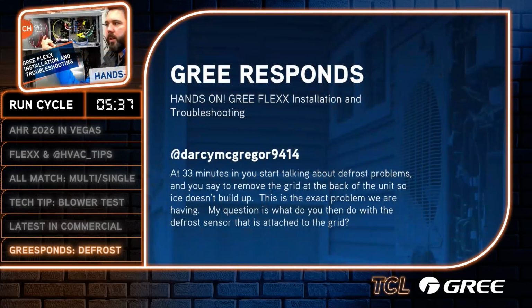It's the hands-on Gree FLEXX installation and troubleshooting video. A viewer commented: at 33 minutes in, you start talking about defrost problems and say to remove the grid at the back of the unit so ice doesn't build up. This is the exact problem we are having. My question is, what do you do then with the defrost sensor that is attached to the grid?